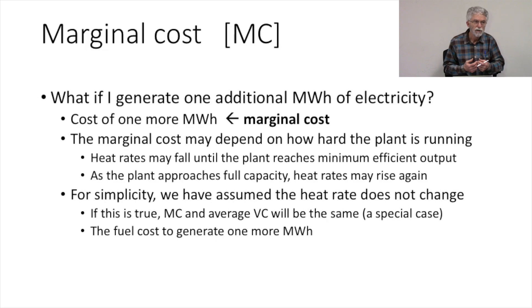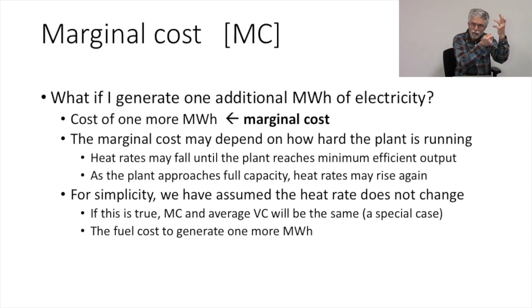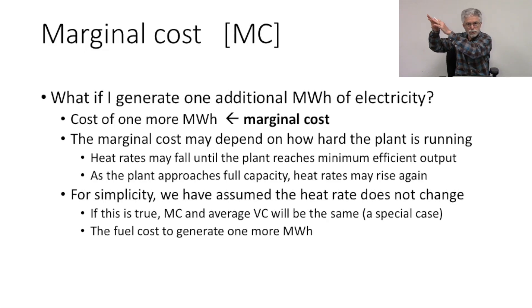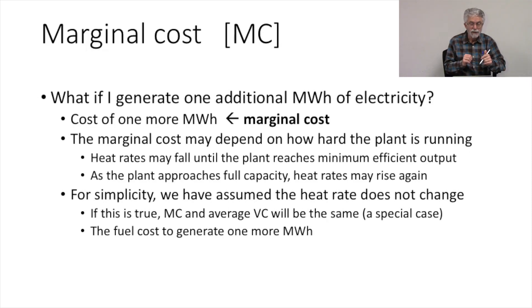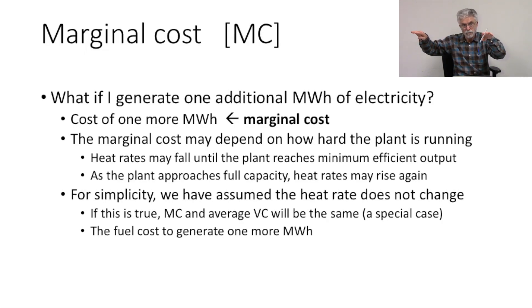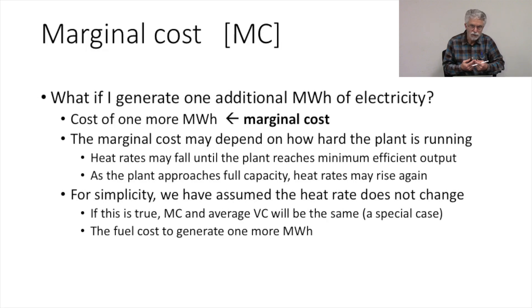You can see right away that marginal cost depends on the heat rate of your power plant. If the heat rate can change, then your marginal cost will change. If you have a really high heat rate, then adding one more megawatt hour will require burning more fuel than if you have a low heat rate. But I'm assuming the heat rate is the same at all capacity factors. So for simplicity's sake, we have a marginal cost that's going to be the same for every capacity factor — this is a simplifying assumption just to make our examples easier to work with.